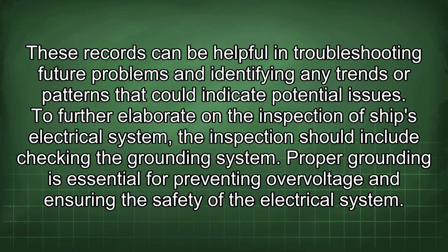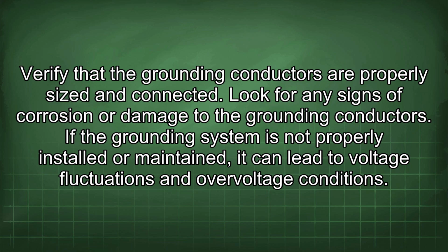To further elaborate on the inspection of the ship's electrical system, the inspection should include checking the grounding system. Proper grounding is essential for preventing overvoltage and ensuring the safety of the electrical system. Verify that the grounding conductors are properly sized and connected. Look for any signs of corrosion or damage to the grounding conductors. If the grounding system is not properly installed or maintained, it can lead to voltage fluctuations and overvoltage conditions.